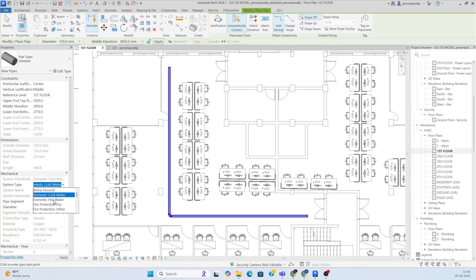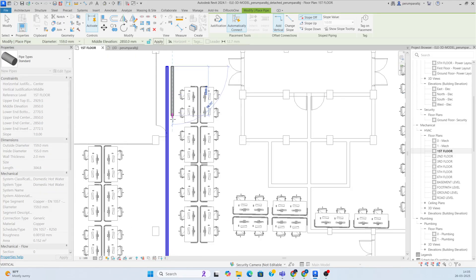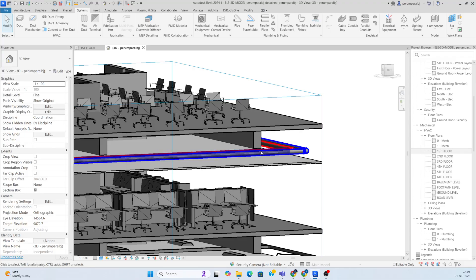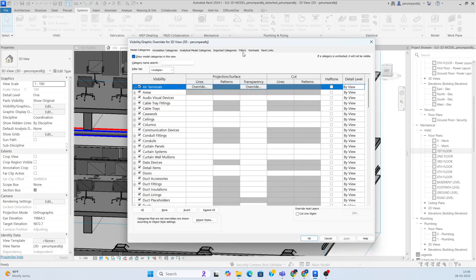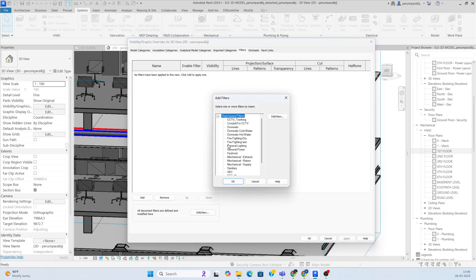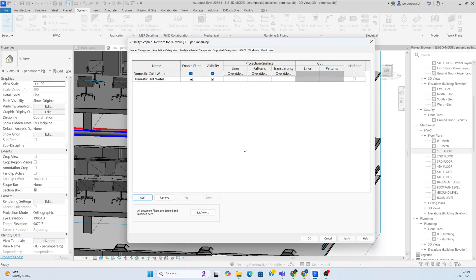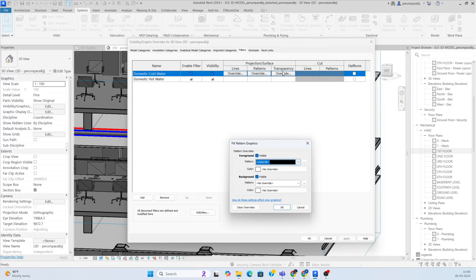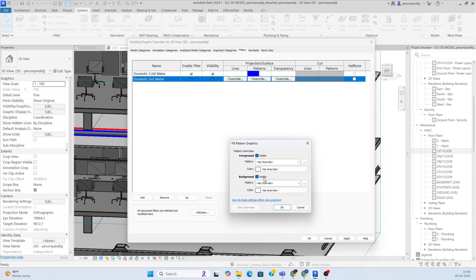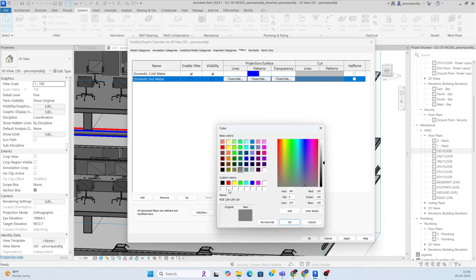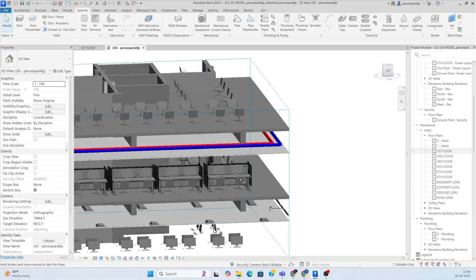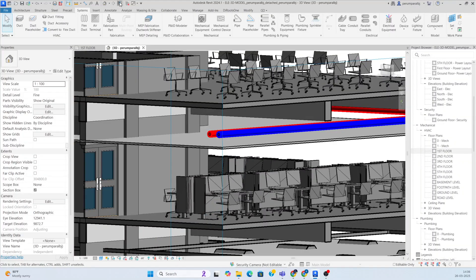Now I need to draw another pipe — this is cold water, so I'll also create domestic hot water. Draw that pipe the same way. In the filter settings, add domestic cold water and domestic hot water. Give cold water a solid fill in blue, and hot water a solid fill in red. Apply and you can see them in 3D.